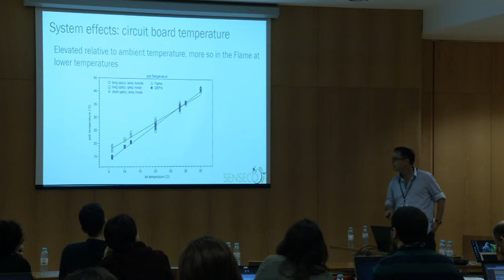Alright, so just summarising that, we can take the mean, of course, because it's a stable mean value of the dark reading across the different ones, and characterise this dark reading response to temperature. It seems pretty consistent across the different configurations of the long and short and inside and outside setups, and the upwelling and downwelling for the flame, but a clear decrease. And as we just saw from the overall spectra, there's not much response in the QE Pro. It's largely stable over the nearly 30 degree temperature range.